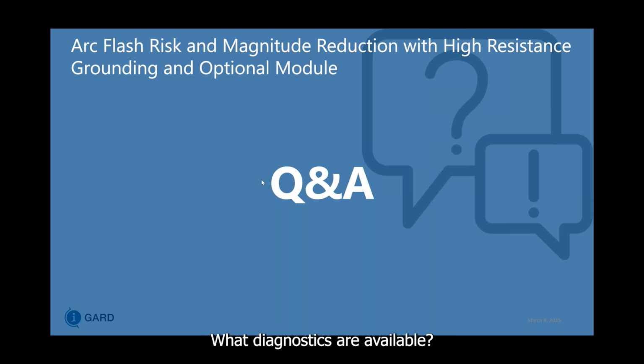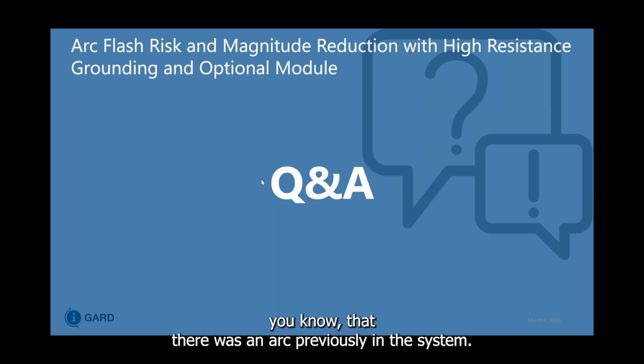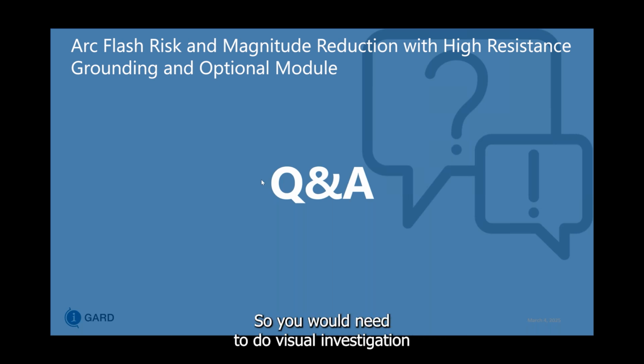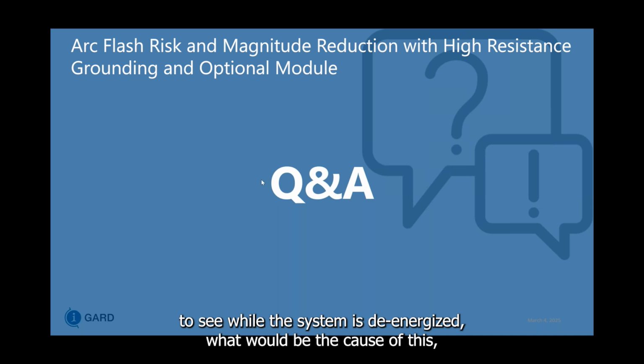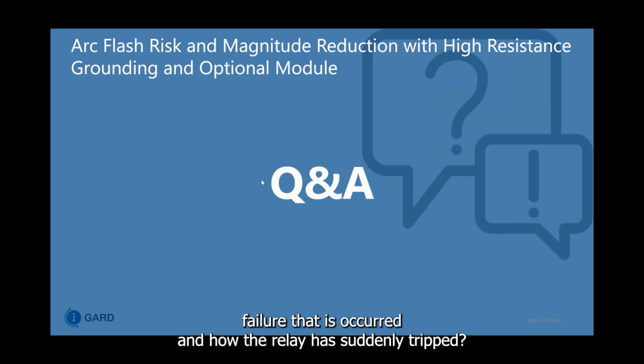What diagnostics are available? For the diagnostic aspects, it's probably mostly visual. When the arc does occur and you see that the tripping is coming from the DSP ADM module, you know that there was an arc previously in the system. So you would need to do a visual investigation, while the system is de-energized, to see what caused this failure and how the relay has suddenly tripped.